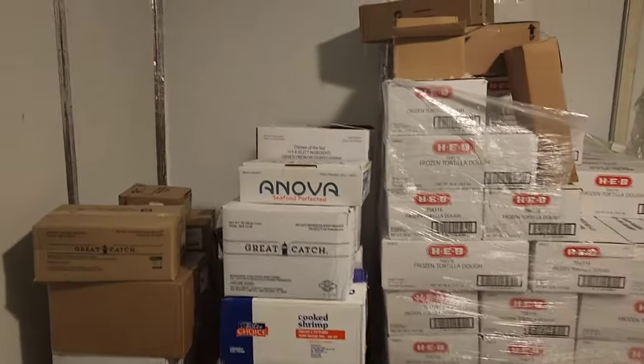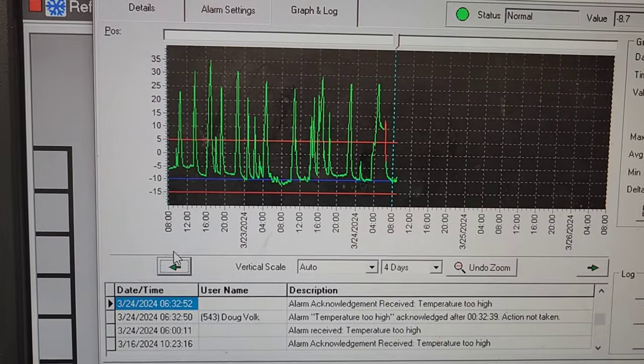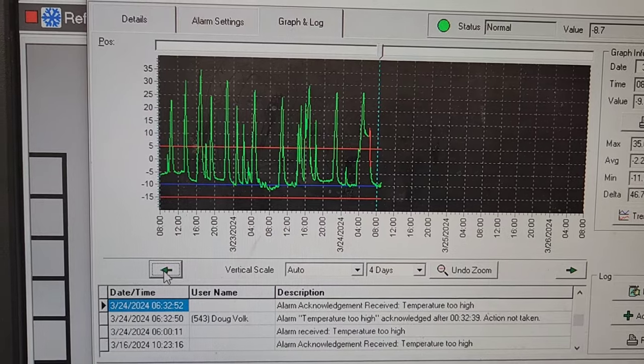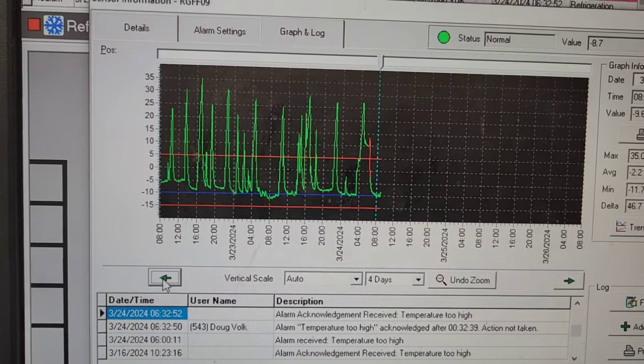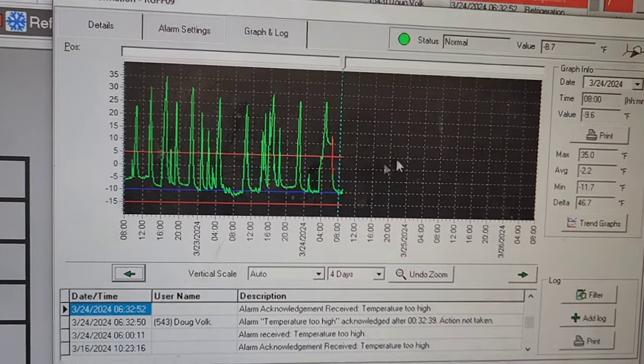Yeah, it sure is freaking cold in here. I don't think there's anything wrong with this freezer. So yeah, it alarmed this morning, but it's negative 10 degrees in there right now. It's negative 8.7.